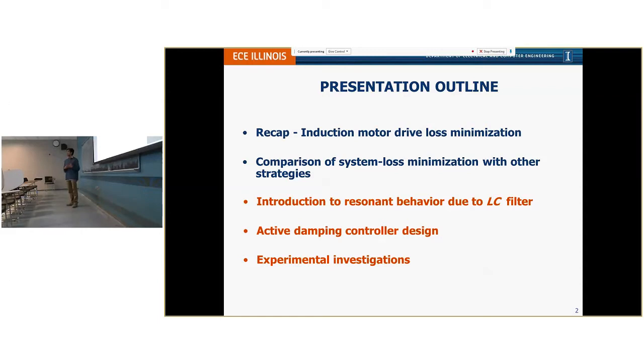The second part of the talk covers something different. Because of the connection of LC filters with induction machine drives, we observe a phenomenon called resonance, and we develop an active damping controller designed to damp these resonant oscillations, because they are very detrimental to the operation of the induction machine drive. This active damping technique is not based on connecting a physical resistance, which obviously incurs loss, but does something else to damp these oscillations.